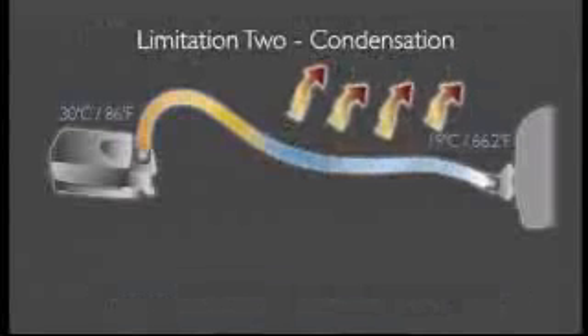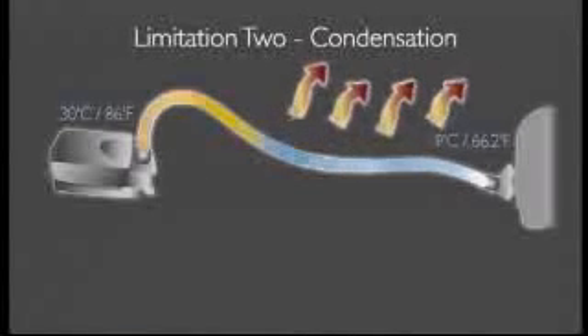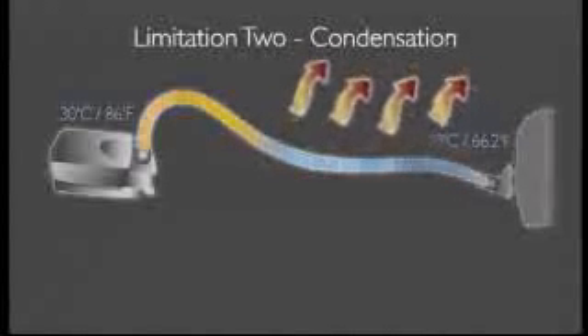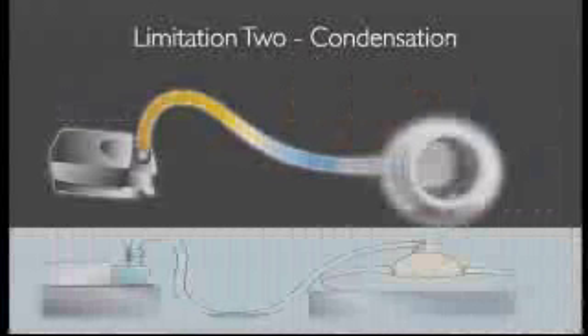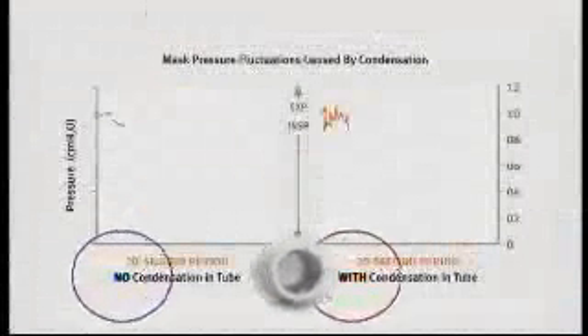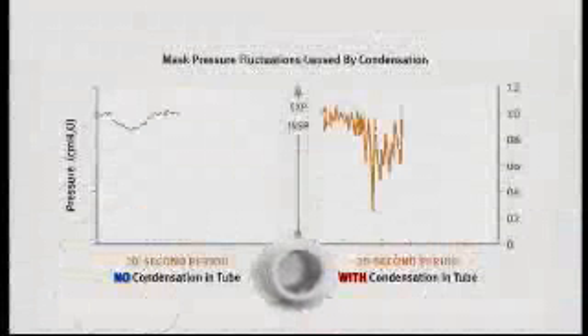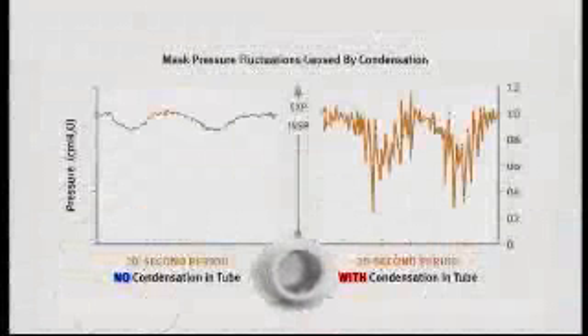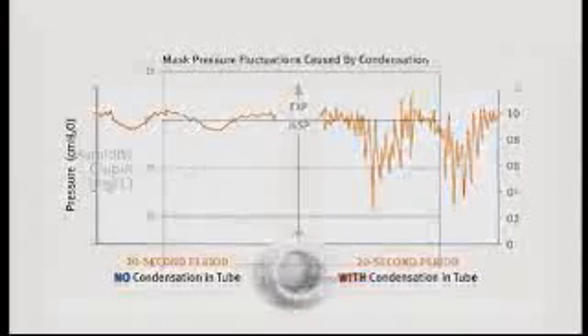The second limitation is condensation. As the warm, moist air travels along the tube, it begins to cool. Eventually, it cools to the point it can no longer carry as much moisture and condensation forms. Condensation results in a disruptive gurgling noise and rapid fluctuations in mask pressure. As little as 2 teaspoons of condensate in the CPAP tube can cause a drop in the pressure delivered to the patient by as much as 5.5 centimeters of water pressure, as shown in this graph.